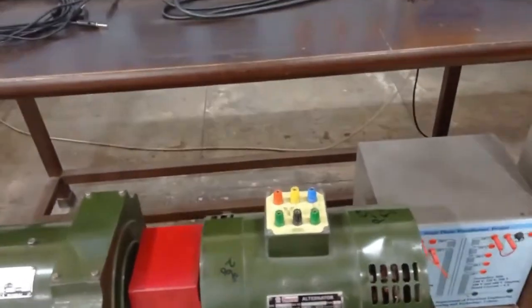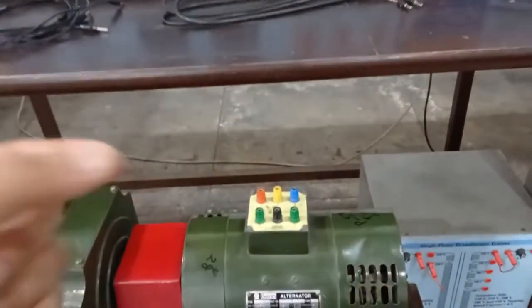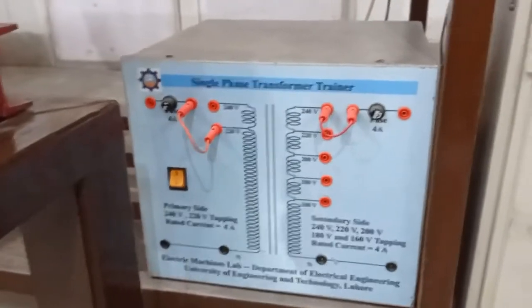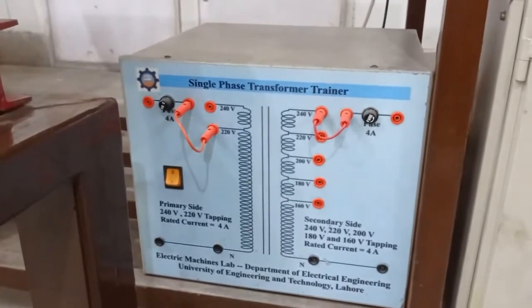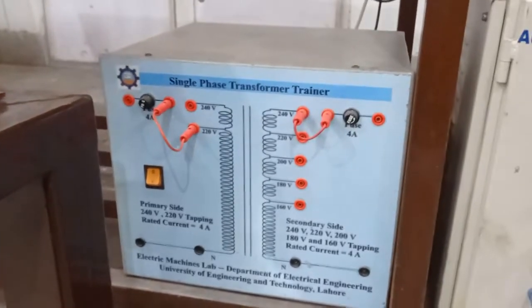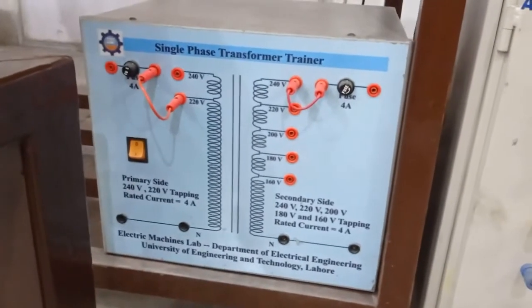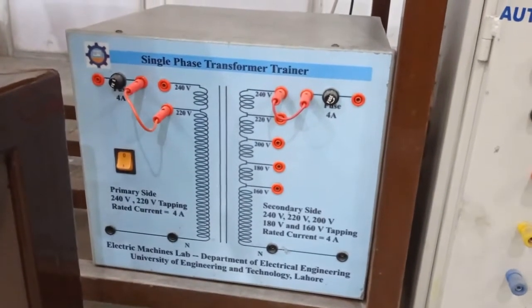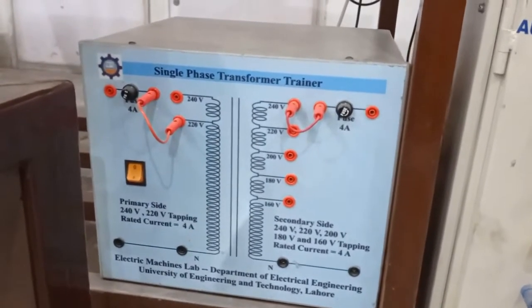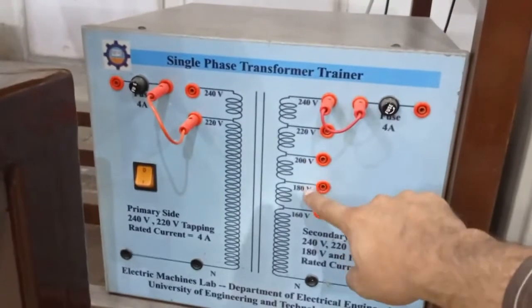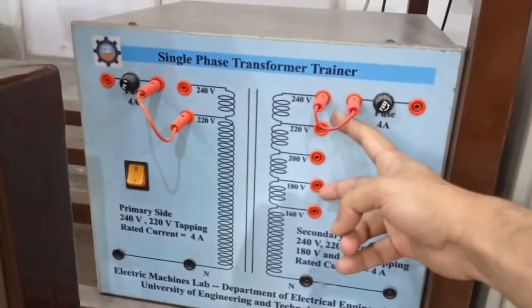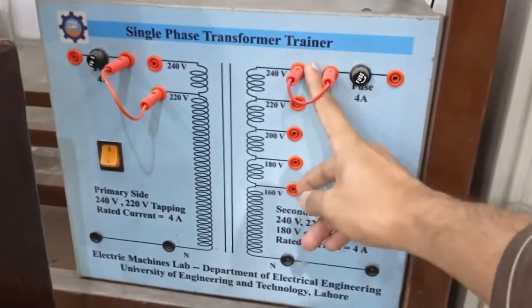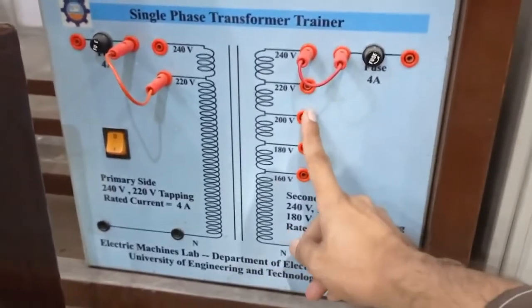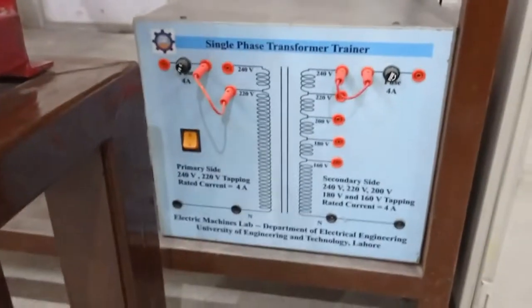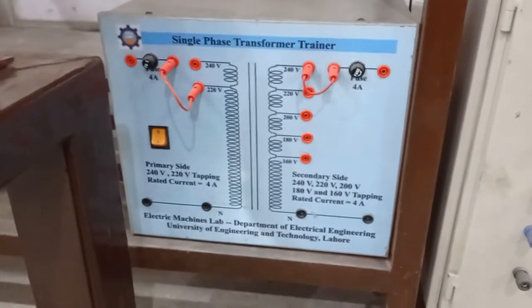Next we are going to connect the neutral of this generator to ground through a grounding transformer. Here this transformer will be used as grounding transformer. It has two available ratings at the primary side, 220 and 240. On the secondary side, a number of taps are available to get 160 volt, 180, 200, 220, 240. Between two consecutive taps the difference of voltage is 20. So we can get 20 volt between these, 40 volt between these, 60 over here, 80 over here, or 160, 180, 200 like this. Now students will connect the primary and secondary according to the instruction given in the manual.